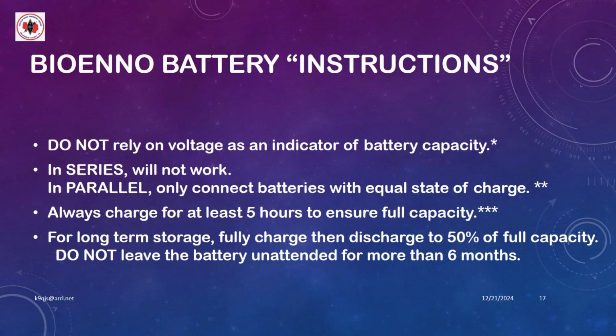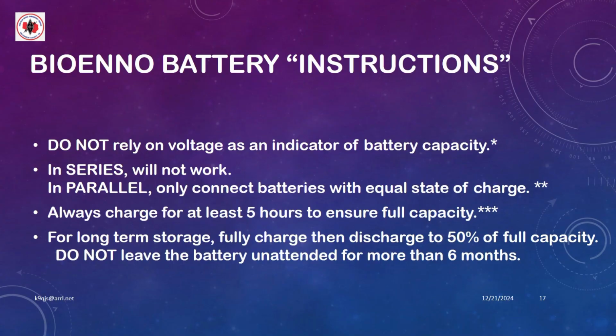The first is you cannot, with a lithium iron phosphate battery, rely on voltage as an indicator of battery capacity. In the slide I showed you a few slides ago, you saw that it's really pretty flat for the life of the battery. So it's almost more important to look at the duration. These batteries will not work in series. They will work in parallel, but there are some constraints. In parallel, you should only connect batteries with an equal state of charge.